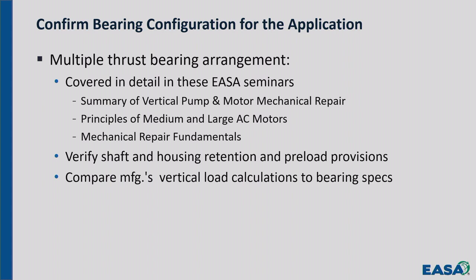Okay? So if you're working on vertical pump motors and you have no knowledge of this, if this is something like the first time you've ever seen it, be aware that this is one of the areas where you can get into trouble when a motor goes back and the customer installs it, if you don't have any knowledge at all about what that vertical load rating is for the bearings in their present configuration. Okay.